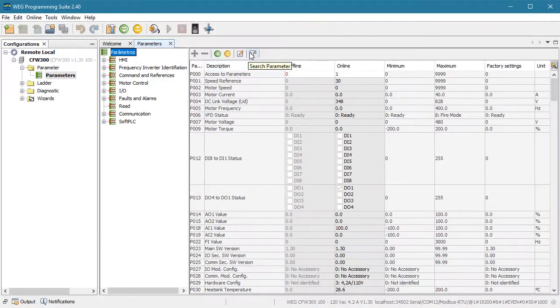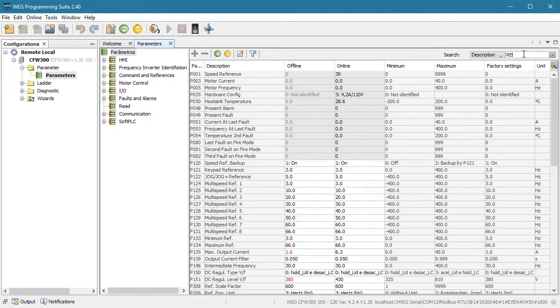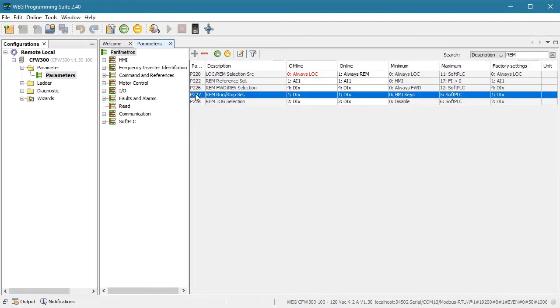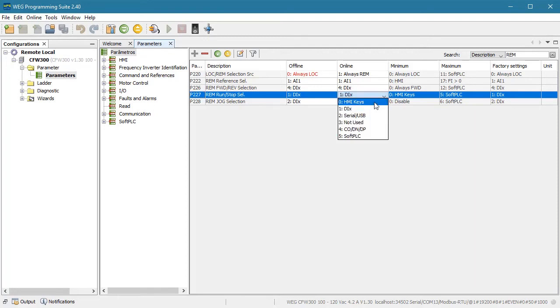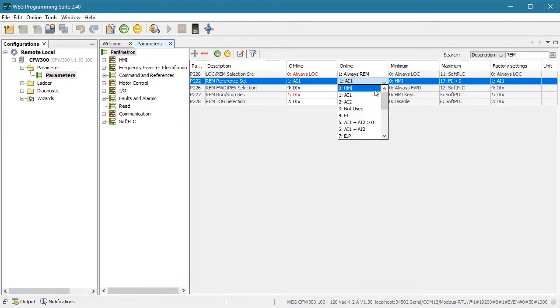If I bring up the free WPS software and search for remote, I see that remote run-stop is controlled by parameter 227 and to change it to being controlled by the HMI, I just need to change it to a zero. I also see that the remote reference frequency source is controlled by parameter 222 and that a zero will change that to HMI control. So, we need to change both of these to a zero.